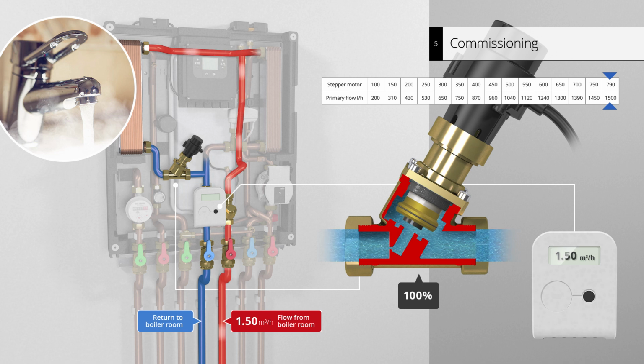As the temperature in the primary return stabilizes, the flow rate can now be cross-referenced with instantaneous primary flow readings on the heat meter. For details how to access the parameters menu and for information on further commissioning steps, please refer to the installation manual.